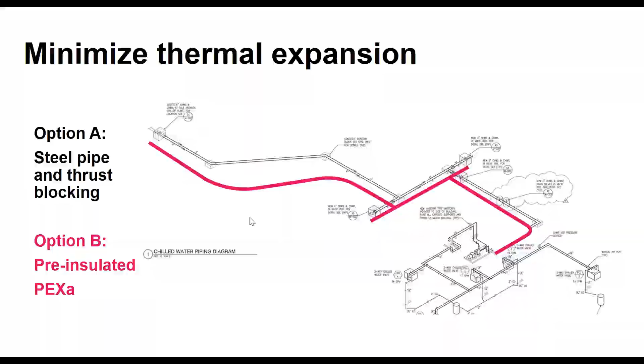The pink line in this slide makes it look a little easier than option A. Exactly—in option A, you have a fitting every 20 to 40 feet, so any offset or change in elevation requires a fitting, whereas straight run pipe gives you the flexibility, literally, to run with minimal fittings. From a quality of life standpoint, it's not that much fun to work in a trench. If you can just roll this pipe into place instead of welding steel down in the dirt and mud all summer, that's a nice improvement for the installing contractor.